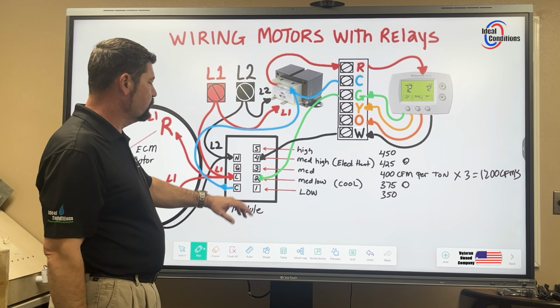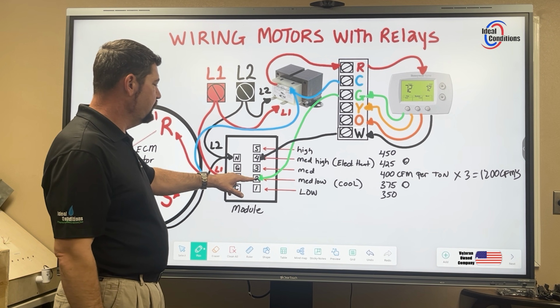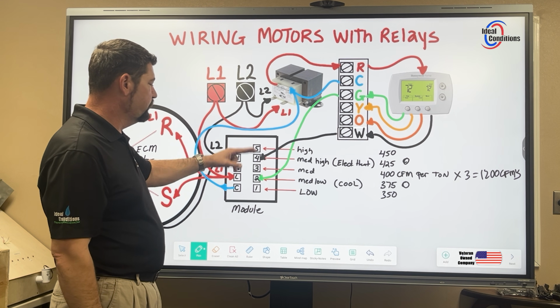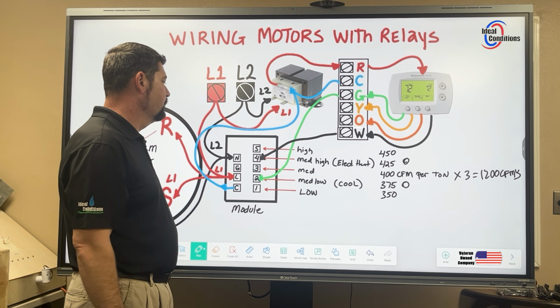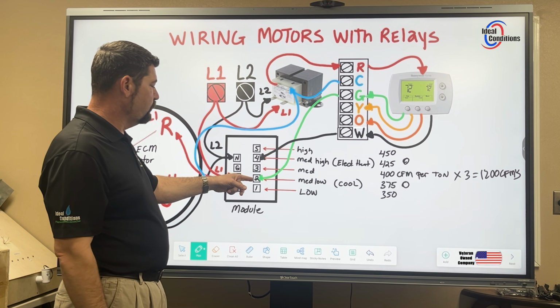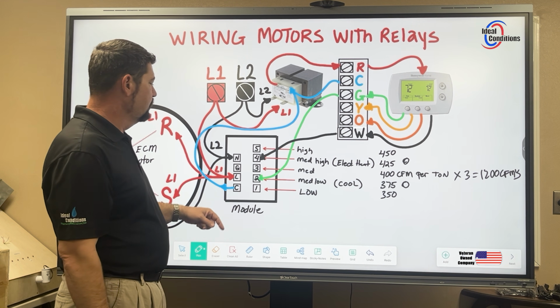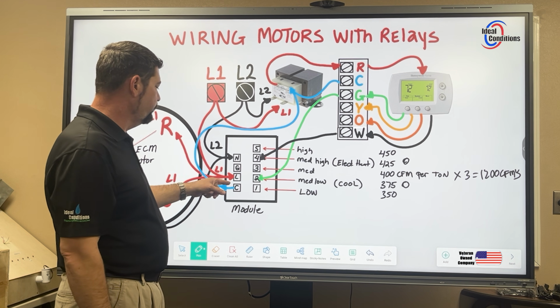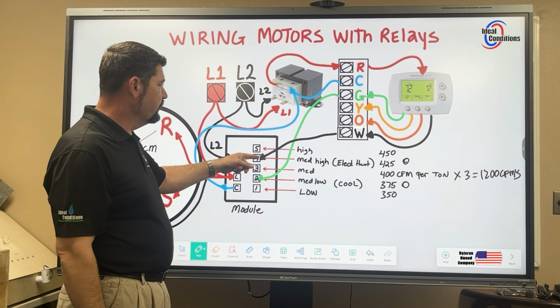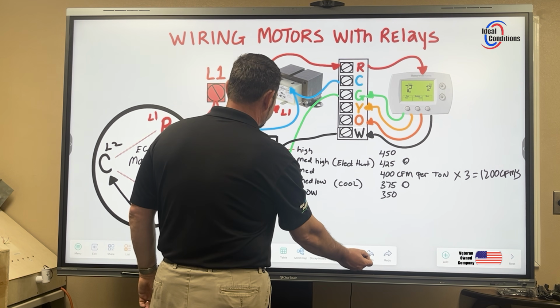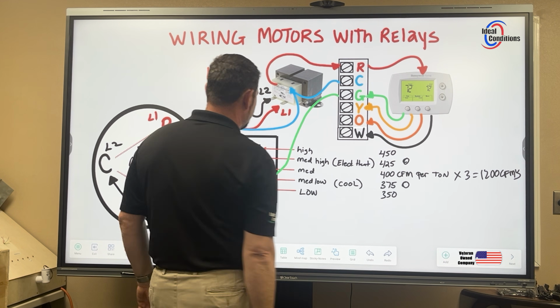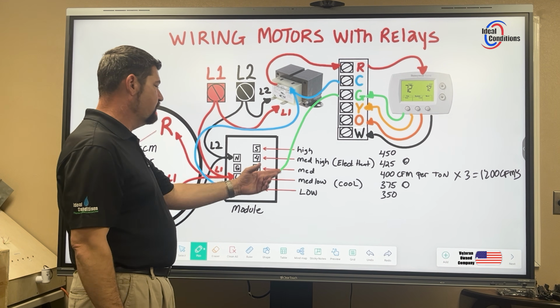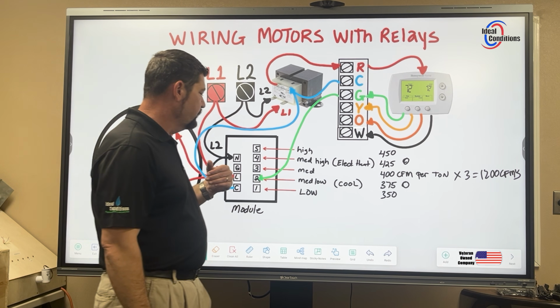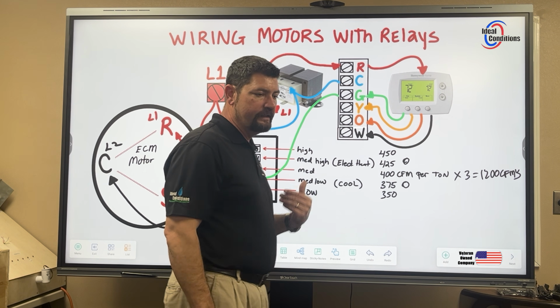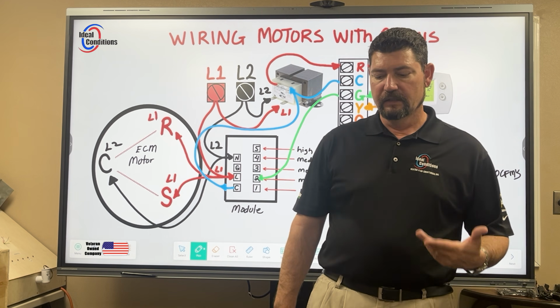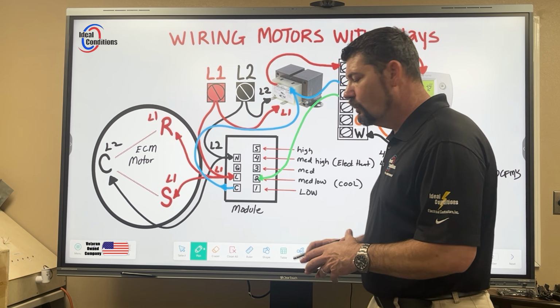And as long as this module is receiving 24 volts here, if it picks up 24 volt, call another one, you will hear that motor pick up. And you'll say, wow, I still have 24 volts between 2 and common, but I also have 24 volts between terminal 4 and common. Well, yeah, if you remove this last step here, it's just going to back its speed back down to medium low. Now, if I lose the G call completely, there's a 90-second countdown. And so I wanted to talk about that because I go over that extensively.